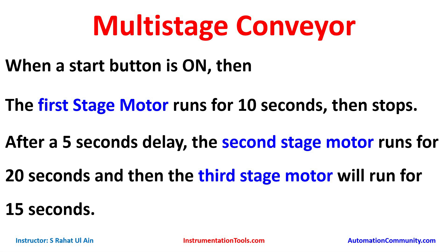After a 5-second delay, the second stage motor runs for 20 seconds, and then the third stage motor will run for 15 seconds. We will use a normally open contact for the start button and timers to keep Motor 1 on for 10 seconds, Motor 2 on after 15 seconds for 20 seconds, and Motor 3 on after 35 seconds for 15 seconds.